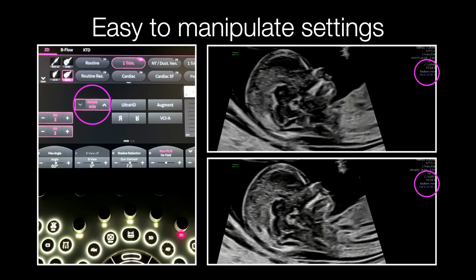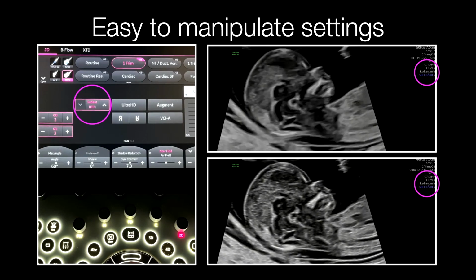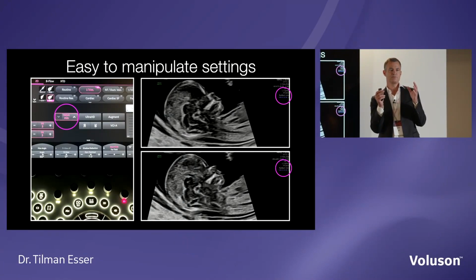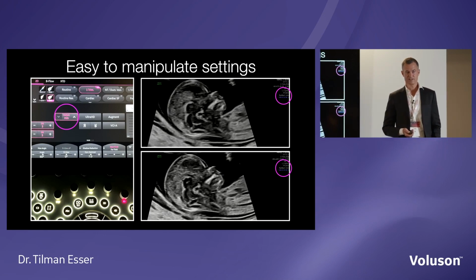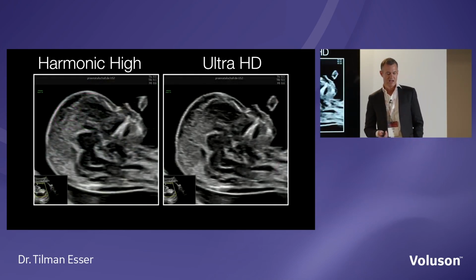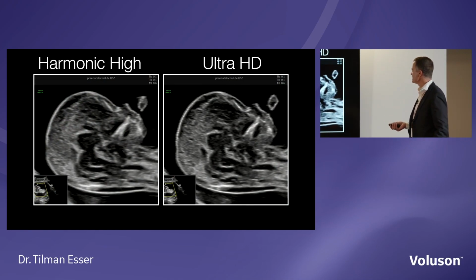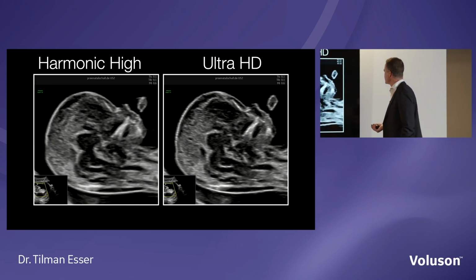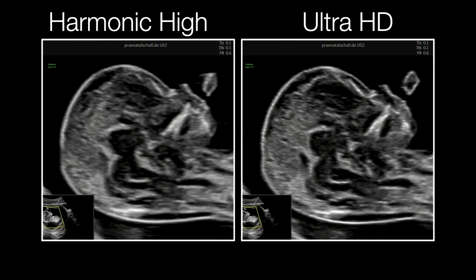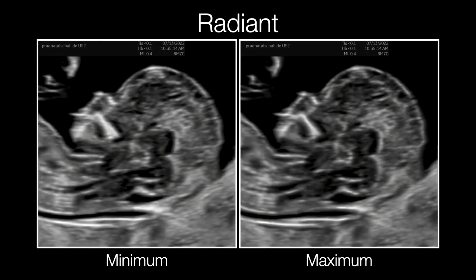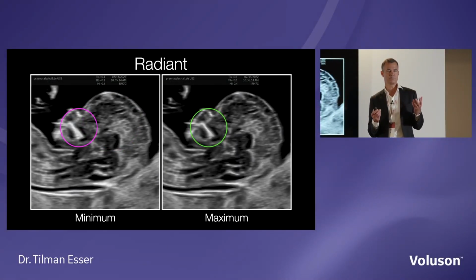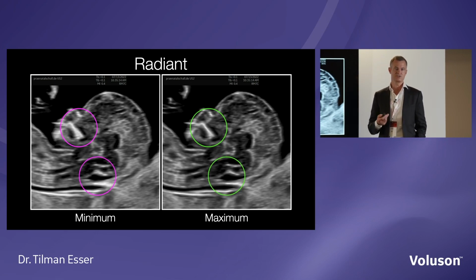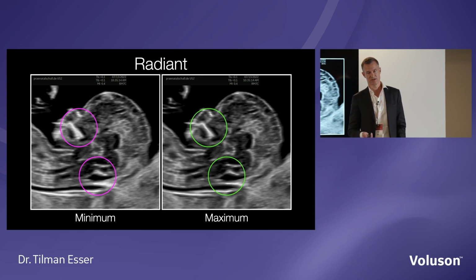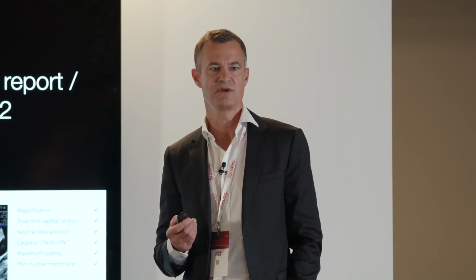A major advantage of the new system is that you choose your preset, you magnify the part you want to examine, and then you can add radiant or ultra HD. Here's another example, harmonic high versus ultra HD, and I think you see the difference, especially when looking at the hard palate and the intracranial structures and the nuchal translucency. Well, what you always have to be aware of is that radiant will change the appearance of your image. So echogenic structures like the hard palate appear thinner, and anechogenic structures like the intracranial translucency and the nuchal translucency appear larger. So this might affect your first trimester screening, your measurement of the nuchal translucency.